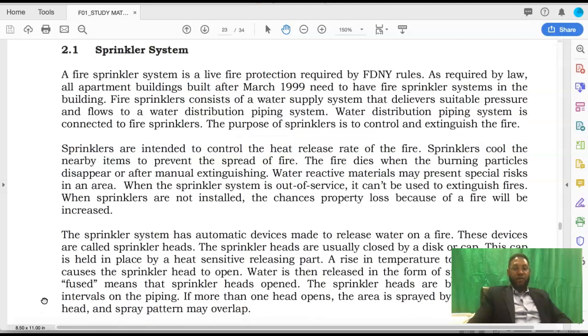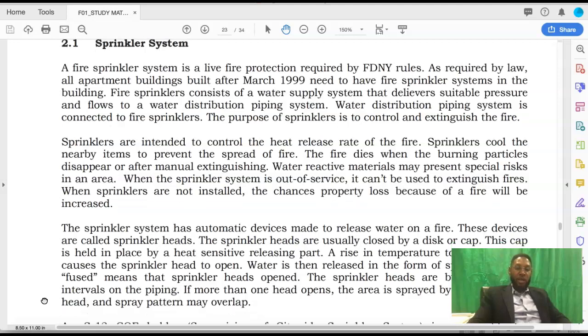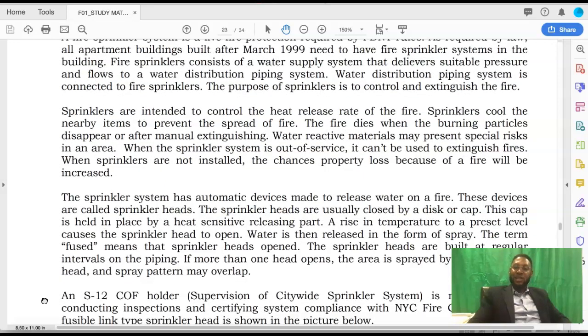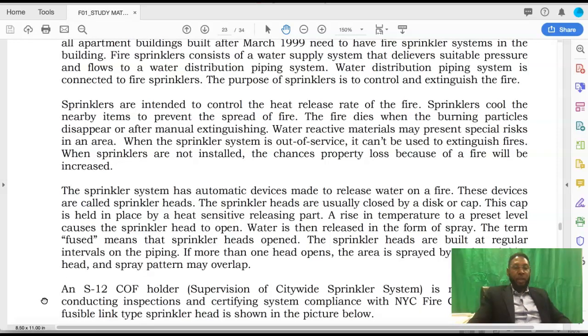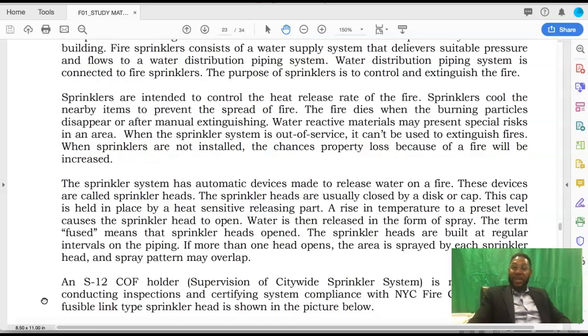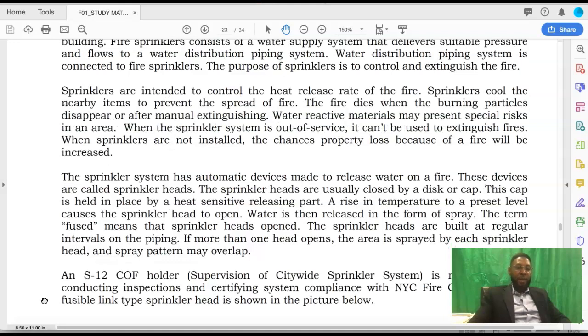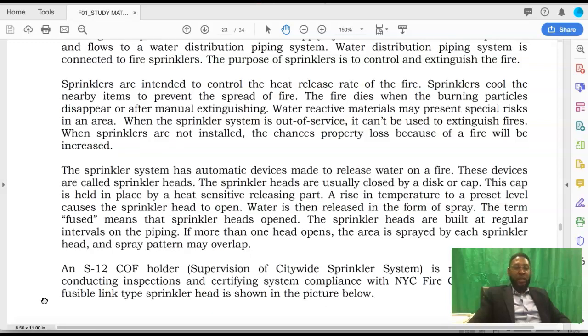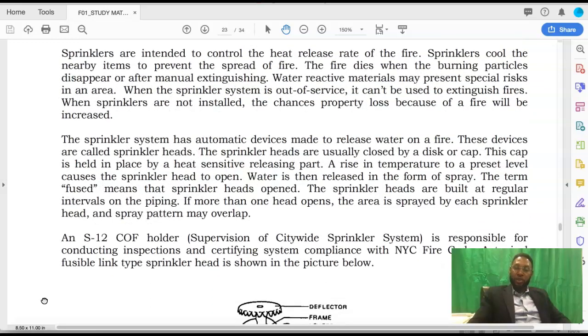Fire sprinklers consist of a water supply system that delivers suitable pressure and flow to the water distribution piping system. The water distribution piping system is connected to the fire sprinklers. The purpose of sprinklers is to control and extinguish the fire in case of any kind of fire in the building. Sprinklers are intended to control the heat release rate of a fire. Sprinklers cool nearby items to prevent the spread of fire. The fire dies when the burning particles disappear and after manual extinguishing.